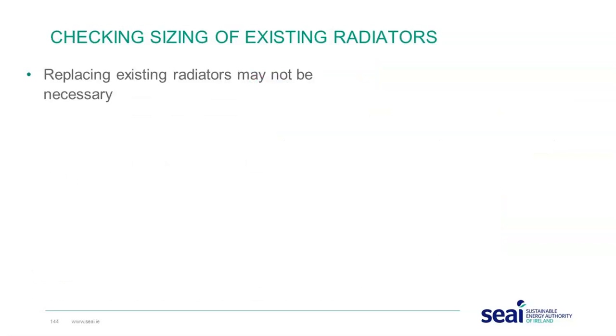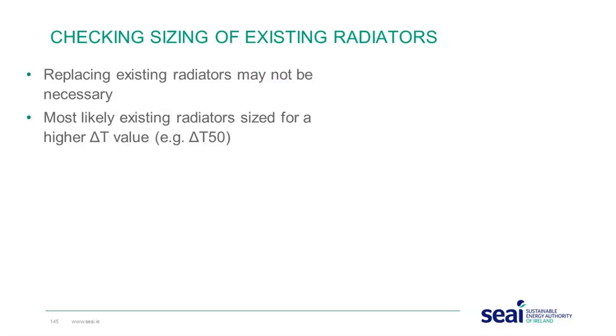So what happens if there are existing radiators? Well, firstly, it may not be necessary to replace existing radiators. It's most likely that existing radiators were sized for a higher delta T value, for example, a delta T of 50. Verification of this sizing for the grant is required. So it's essential that you verify the size and the output of the radiator and provide that information.